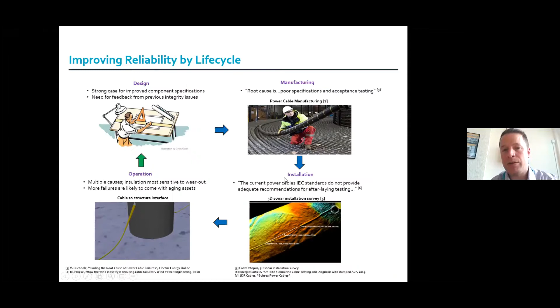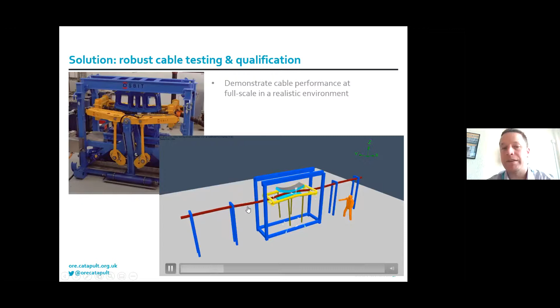So how do you make sure that cables are okay? Well, you can test them. So this is our dynamic test rig, and this is an OrcaFlex model of that test rig. And essentially you can just bend the cable as it would be bent in service. So you choose a radius, and I think in this case it's about a 2 meter bend radius, and you give it about 1 million cycles, so many months of testing with this bend radius. And then when you finish, you break the cable down, so you cut it into layers and see if anything's broken. Quite a rough test actually, but there are ways also that you can monitor the cable during a test to validate things like your bend stiffness model and also your fatigue model as well. And this is what we're working towards, a final way of ensuring cable integrity.